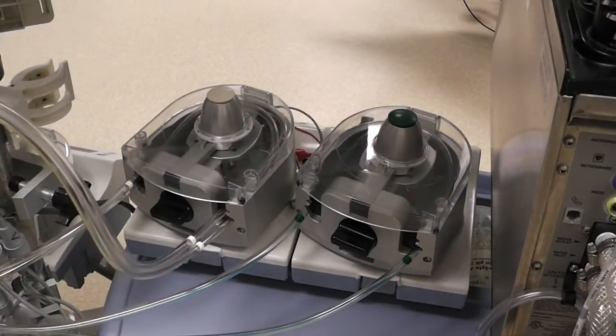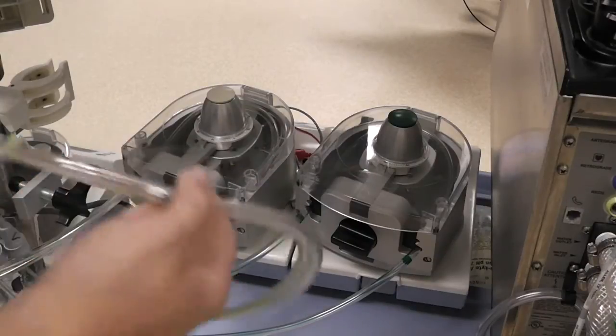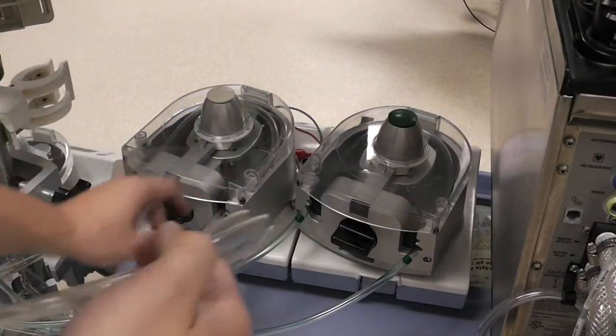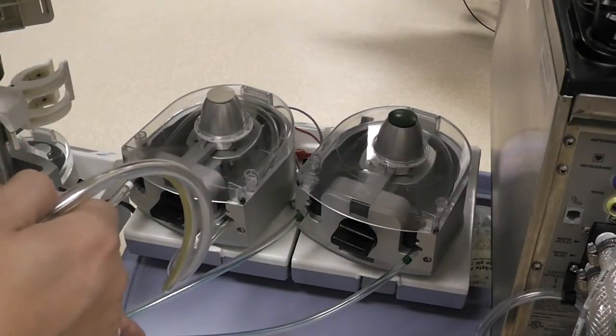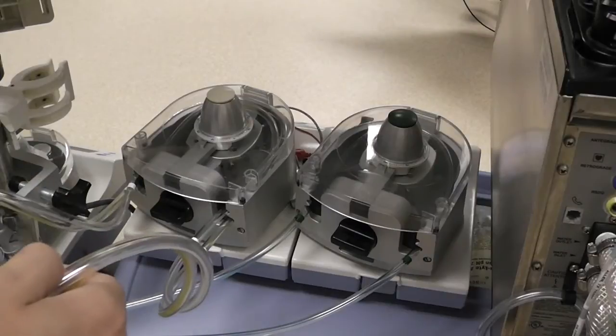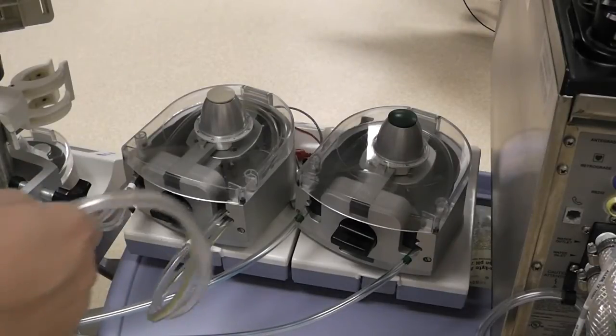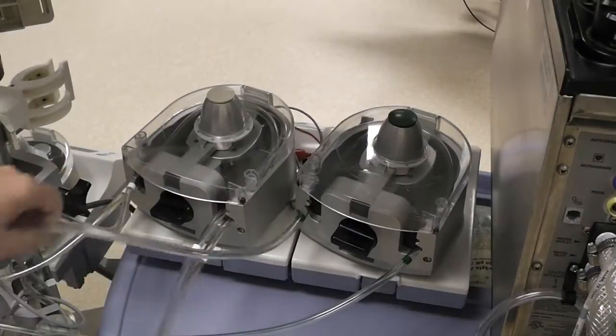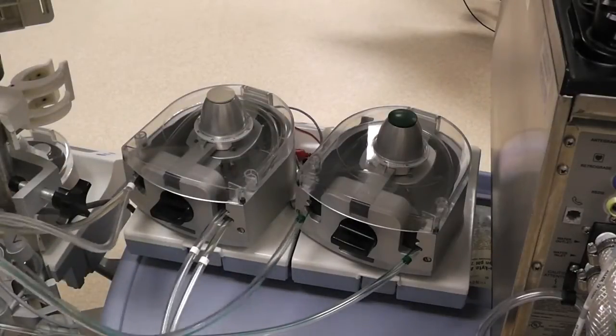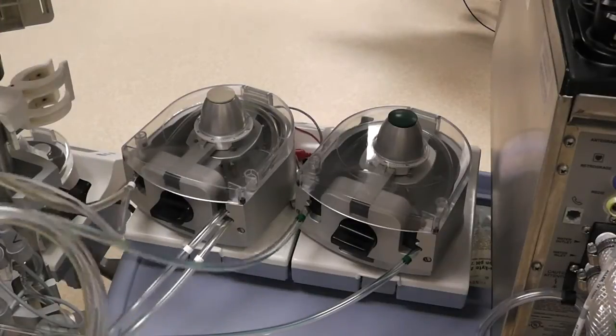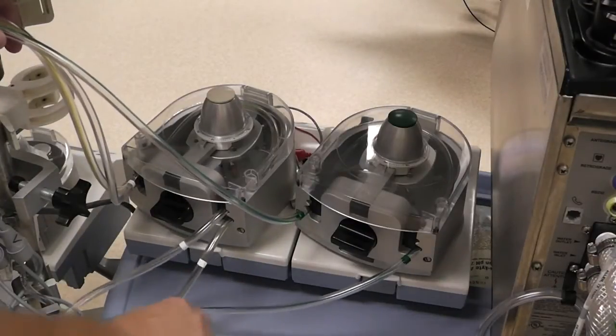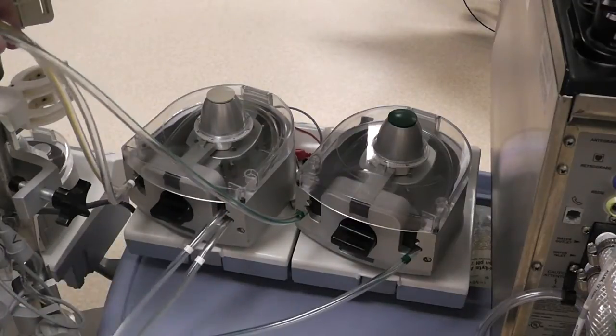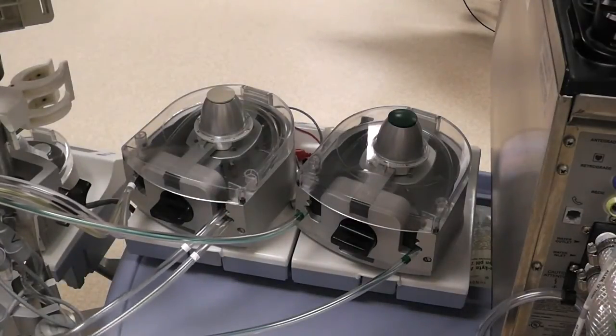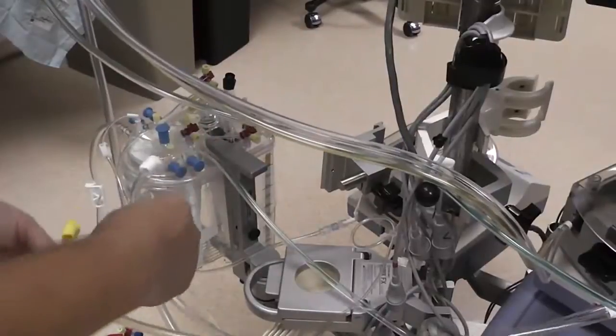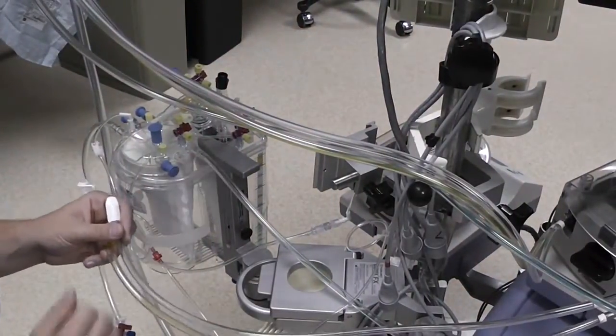Now this is a point where a lot of students make a mistake, and they leave this outflow side going over the inlet of the vent, and you want all the inlet lines on top of all the outflow lines. So we're going to put these under the vent inflow. So you'll see we have the sucker lines on top, the inflow vent line on top, and all of the outflow lines are at the bottom. And now we're just going to make the connection at the back of the cardiotomy for these two lines, just as with the vent.